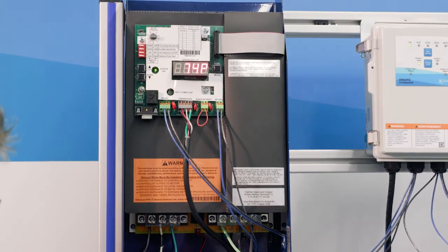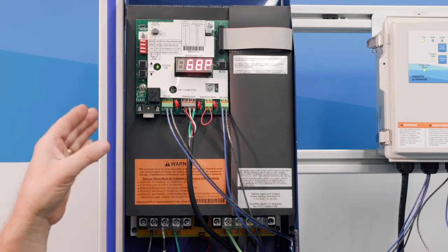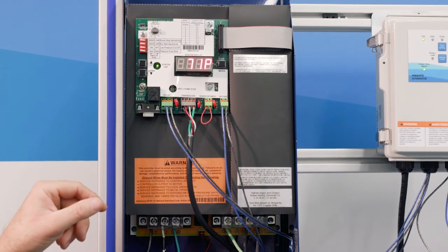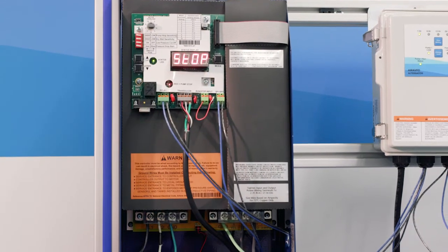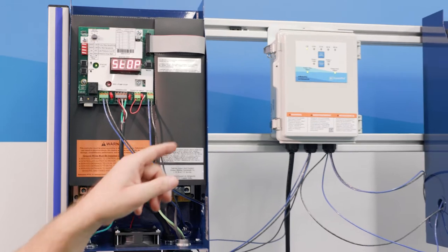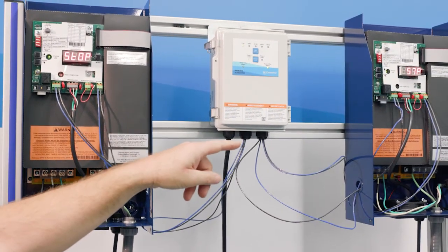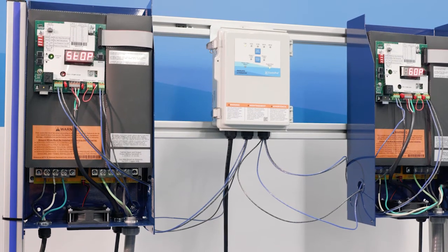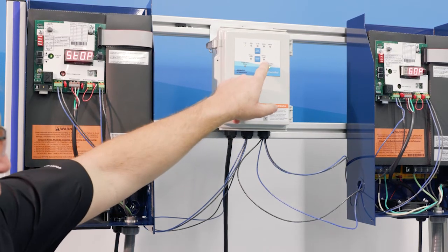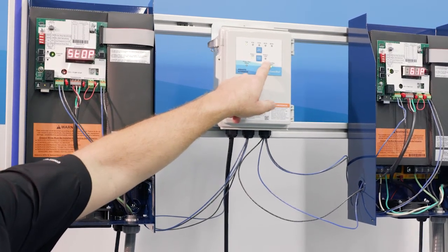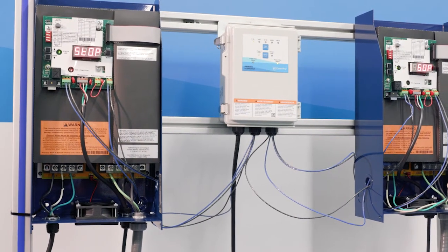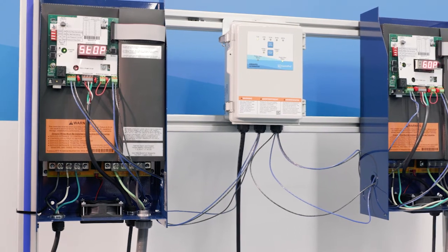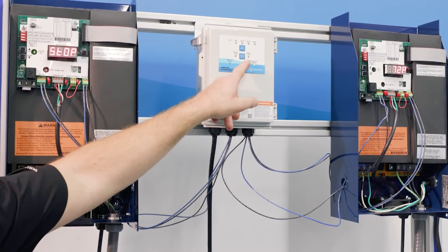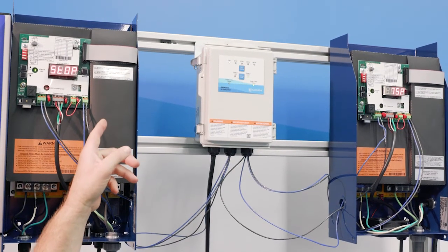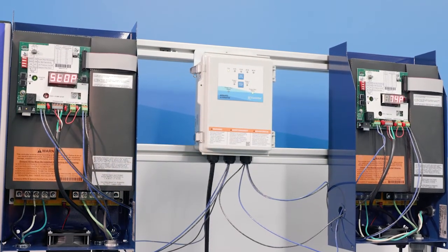So I am going to open up the valve. We can see the lead pump turns on. All right, so let's just open it. And we can see that pump 2 is running. And it waits for 20 seconds. Then what you'll see is the lag will become the lead. So it'll switch. We can see that after 20 seconds it switched because it knew we had a problem with the lead, and it automatically turned our lag into the lead.